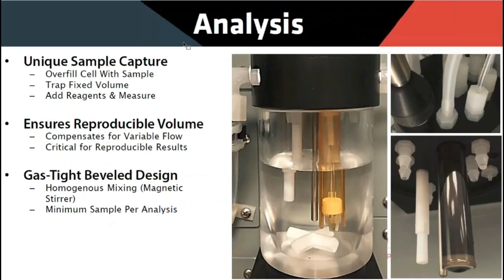The analysis is performed with a very unique sample capture technique, where we overfill the cell with sample and we trap a fixed volume by dropping it down to the required sample volume, 5 mils, 10 mils, whatever it is. And then we add the reagents and perform the measurement. And so what this does is it compensates for any variable flow from old filters or bad flow rates. And this is very critical for getting reproducible results. Looking at the design for the reaction cell, it's a gas-tight bevel design, which reduces the sample required for each analysis.